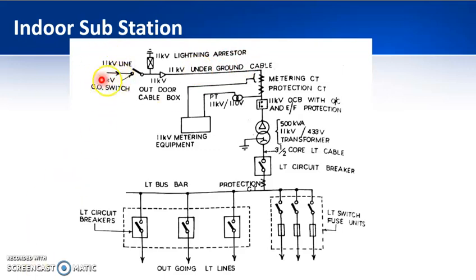Here you can see that you are receiving an 11 kV supply from the transmission or distribution lines running beside the industry where you are keeping your indoor substation. First you will have an air break switch, which is the gang-operated switch used for connecting or disconnecting the supply — making or breaking the supply. Then you will have an 11 kV lightning arrestor.